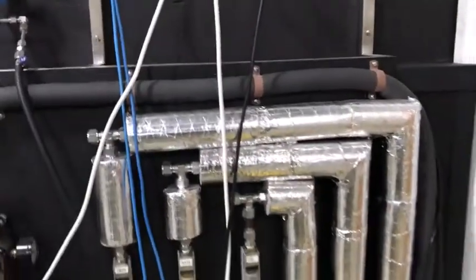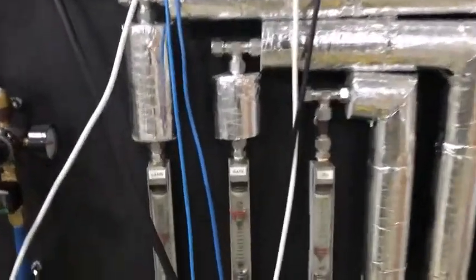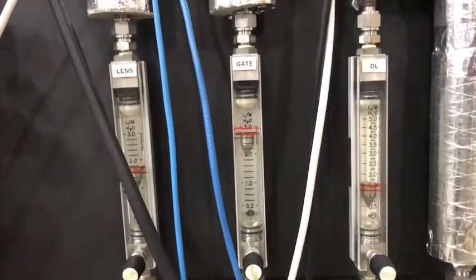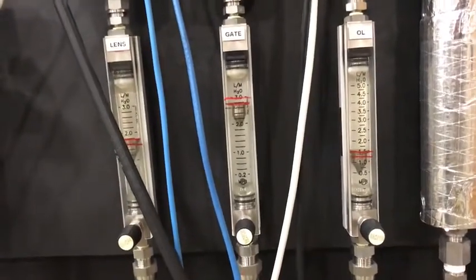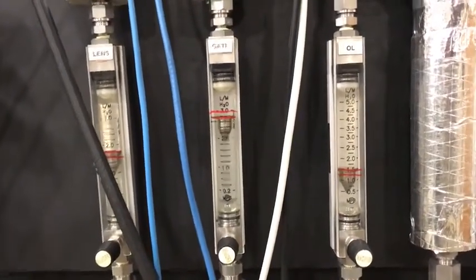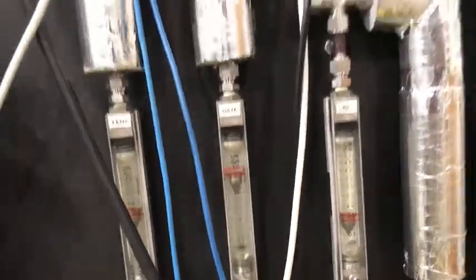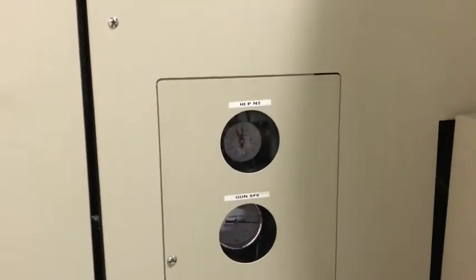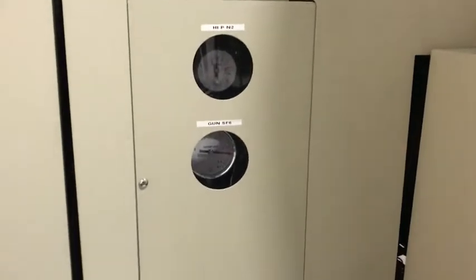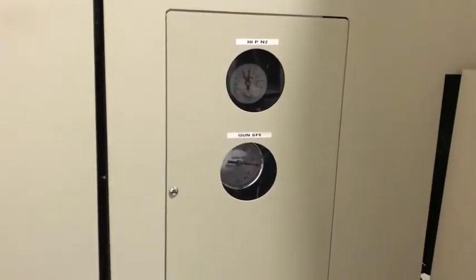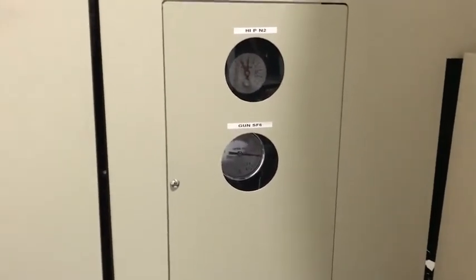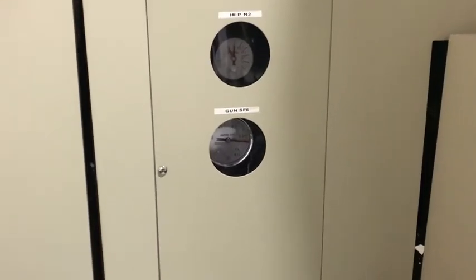We'll check the water. Okay, so this is chilled water that services the microscope lenses. All of those little bobs are up to the line, so we can check that off. Next we need to check gas pressures. So there's the high pressure nitrogen, and that looks right, that's at 12 o'clock. There's the gun sulfur hexafluoride, which is an insulating gas. That's right on the red mark, so that's fine.